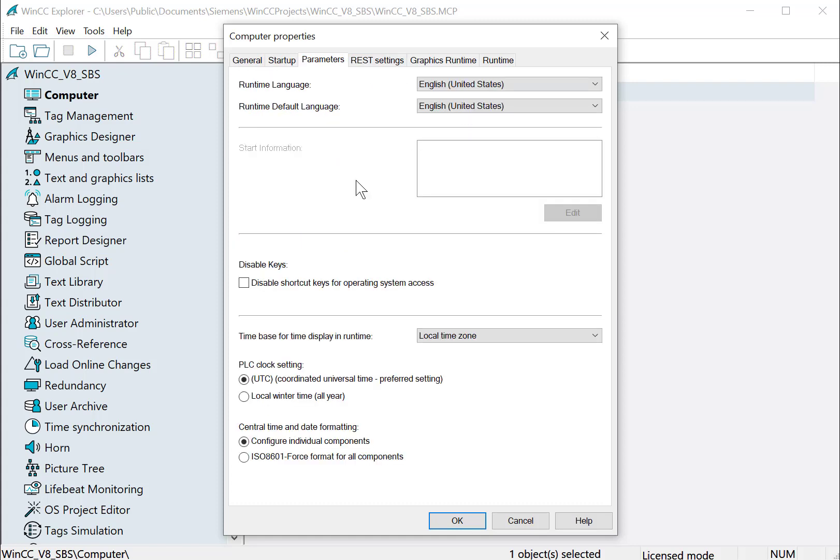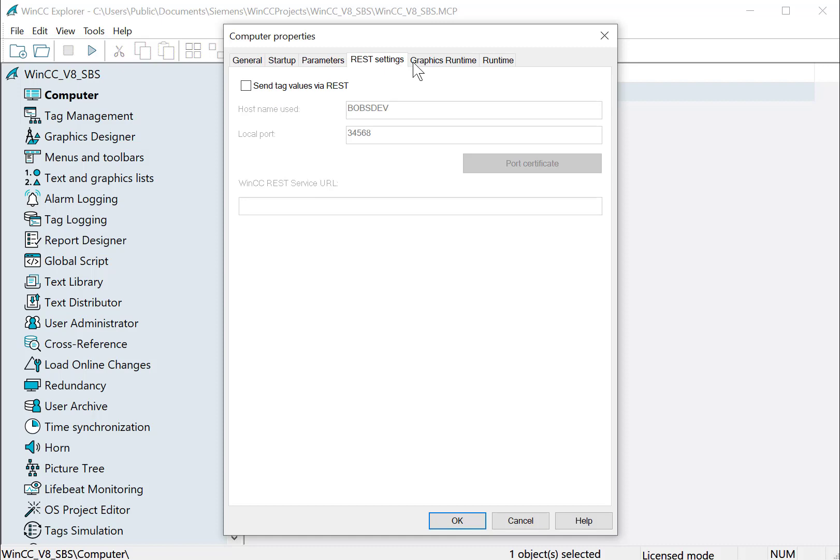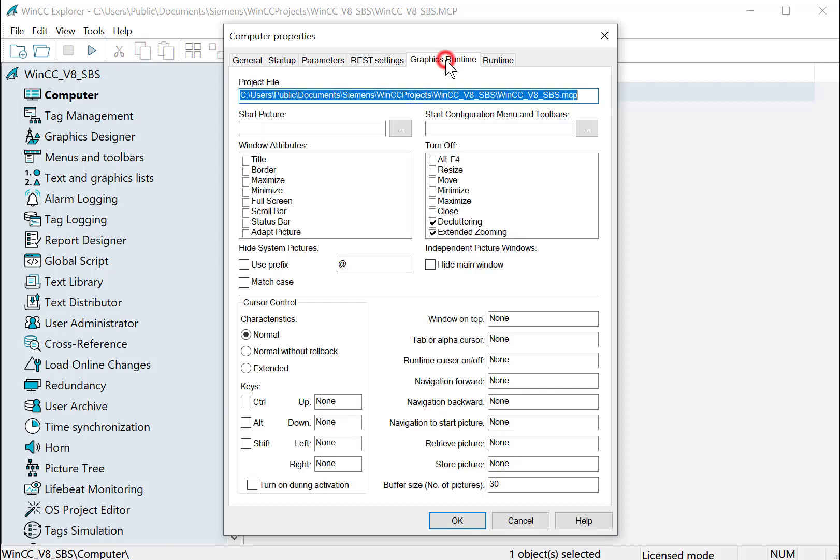Under parameters, we can disable hotkeys to keep the operator out of the operating system while we're in runtime. We set our time zone. Also the new REST interface that we're going to be covering later. And graphics runtime, what our start picture is, menus and toolbars, and attributes of our base UI screen.